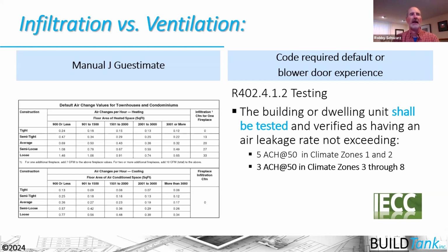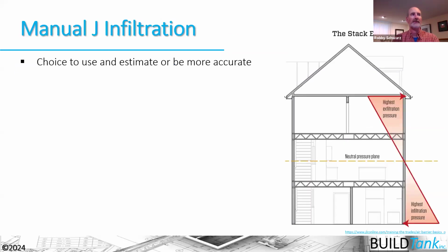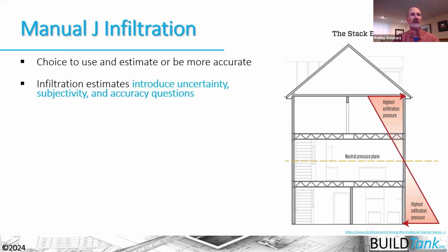loads here. So what we know is that our houses have to be tested and that our houses can't leak more than 3 air changes at 50 pascals of pressure across the building thermal envelope there. So we know that infiltration is a measured load, and we can take that into account in our Manual J. Ventilation is also calculated and put in there, but we also now in the 2021 have to measure that load as well here. So the Manual J gives us a couple different ways to look at infiltration. We have infiltration that is estimated, which gives this level of uncertainty, subjectivity, and inaccuracy in the calculation there that we're looking at.